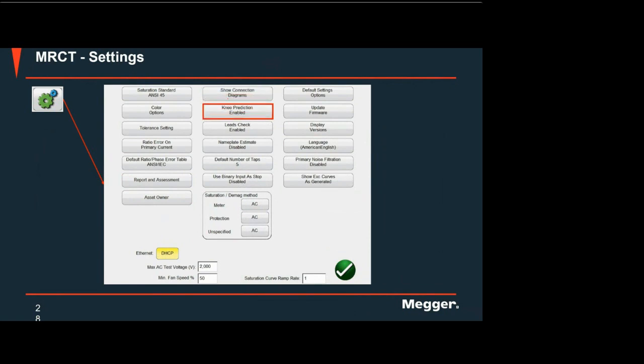You have the knee point prediction. If it is enabled, then you will have a faster testing duration because it will already calculate the next point, just like that. Also, it has the leads check enabled, to check whether your connection is good. Then you have the nameplate estimate, as we discussed in our case study. This is what we use. Of course, the number of taps if you want.